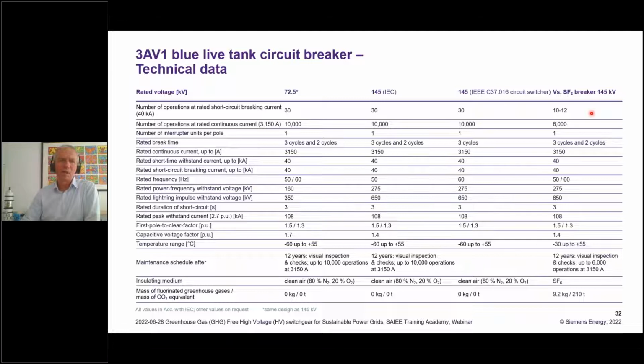Looking at the different capabilities in the technical data, on the right column you see a classical SF6 breaker, 145 kV, with the capabilities of short circuit breaking currents, number of operations, rated break time, and the different characteristics and technical data down here. And next to it, you see the 145 kV vacuum interrupter and clean air technology. And you see very clearly that it is superior to SF6 technology in the number of operations at rated short circuits. It has a higher number of operations for the rated continuous current, from 6,000 to 10,000.